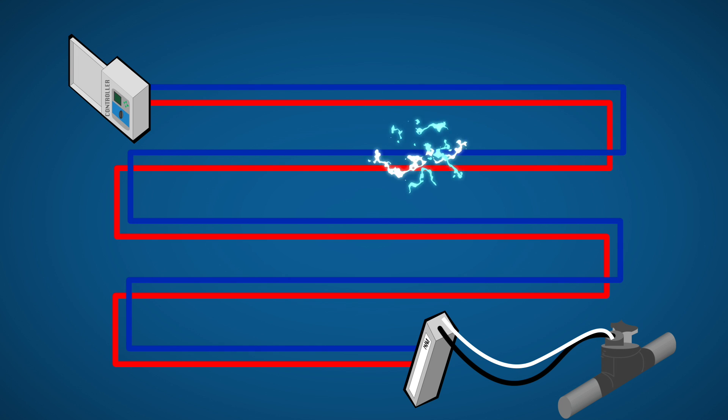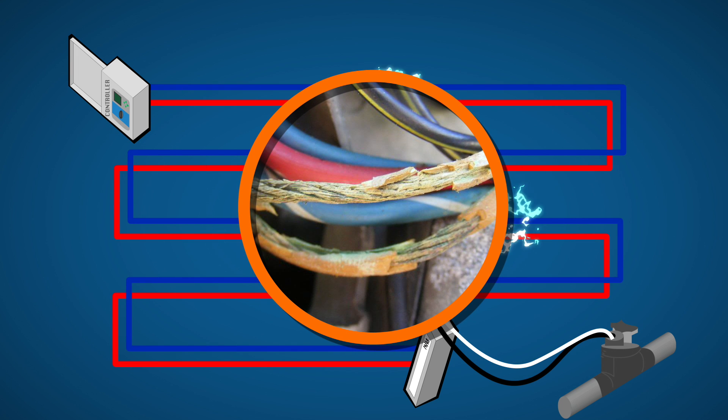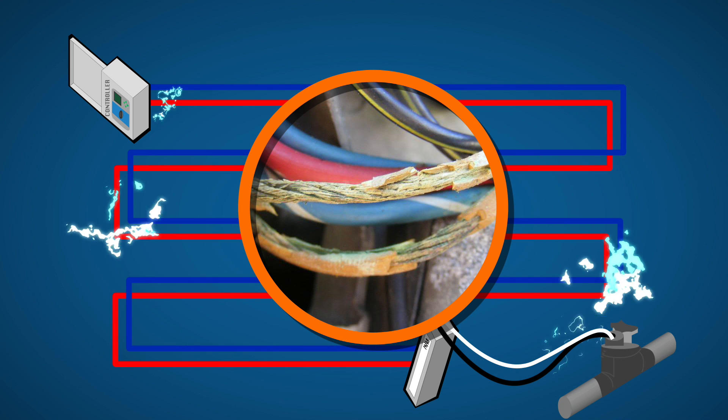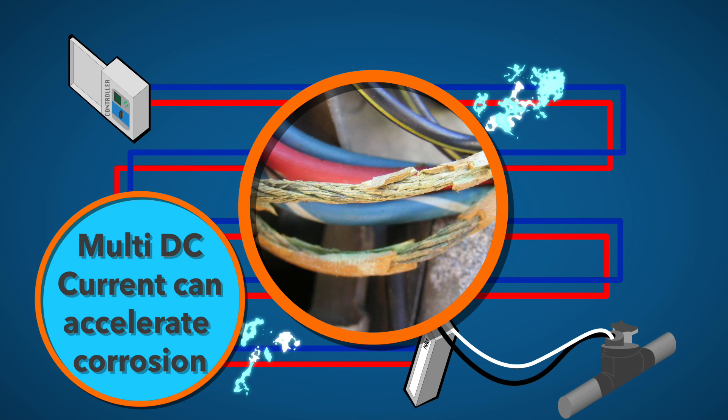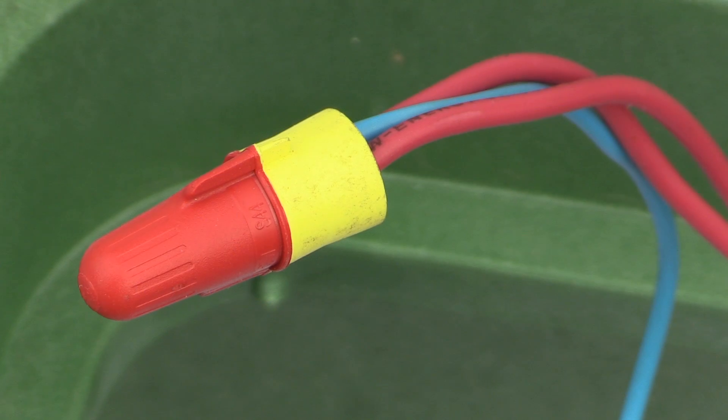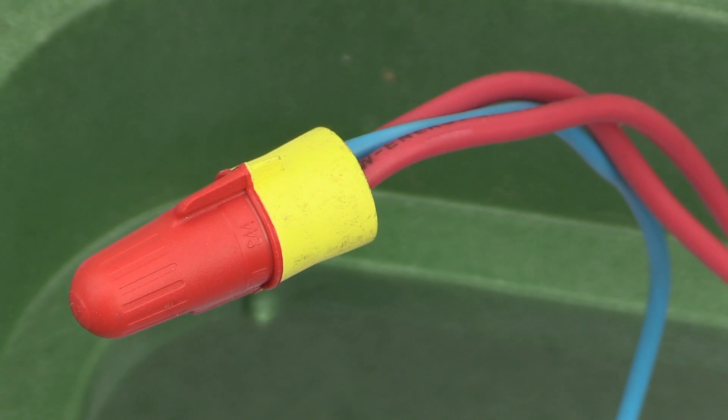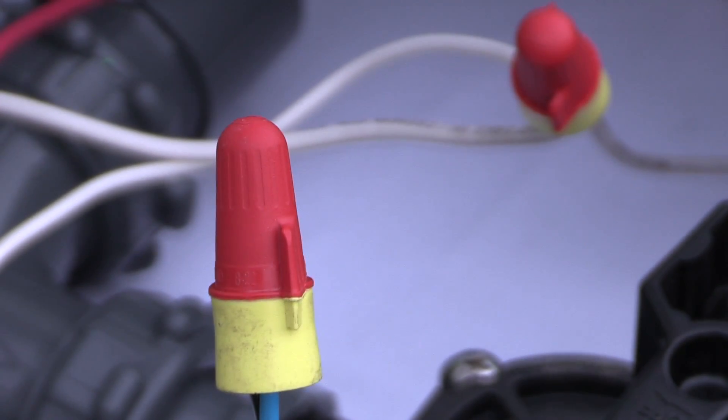Because the wire loop is continually energized in most decoder systems, corrosion can be a powerful enemy to these wire splices. Many two-wire systems use a multi or modified DC current, which can accelerate corrosion of poor splices and causes wires to separate. In many cases, you will find corrosive dust or separated wires in valve boxes where splices were made improperly.